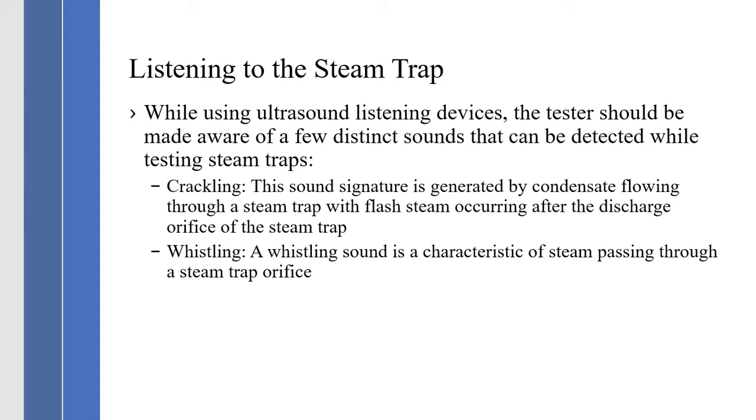until people do it for 2 years. After that, you can watch the meter and take your dB readings, but you can associate the meter readings with the sounds that are occurring in the steam trap. I always watch people and look at their meters, and I can tell them exactly what they're hearing in the steam trap. So.